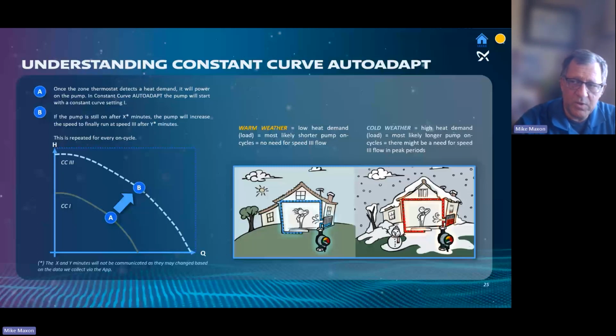If it's that really, really cold day, the pump's still going to be running after a considerable amount of time. I believe after 45 minutes, if it says it's still running, it must really be cold. And that's when it's going to start speeding up. It'll speed up slowly, all the way up to max speed, so that now we can make sure we get more water delivered to that zone, more heat delivered to that zone.